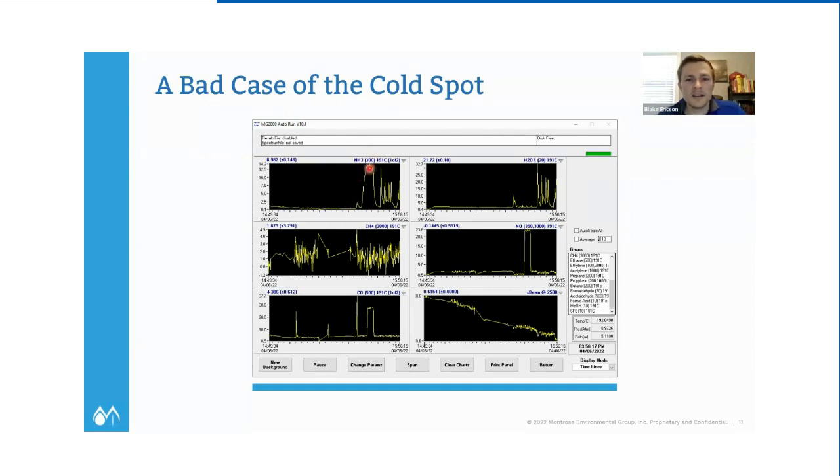And you're going to see things like this where you're sampling, ammonia comes up and boom, comes down where it should be zero, but then it keeps popping up and down. And you see this, it matches the water almost perfectly. That's just because ammonia is water soluble. And when it's at a certain temperature in the heated sample lines, you're going to get this sort of action. So this was a huge indication that there was a cold spot. That heated line needed to be fixed. But it's a really nice representation that some gases behave a lot differently than others, and why it's so important to make sure you're running hot and fast through your FTIR sampling system.